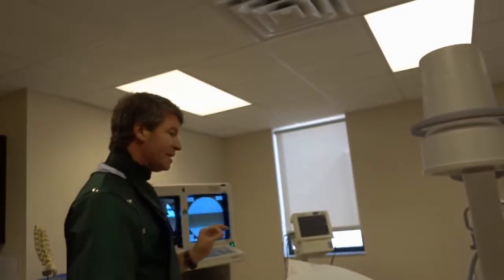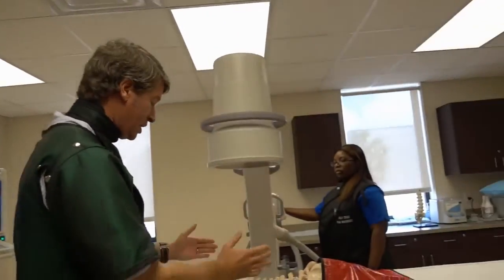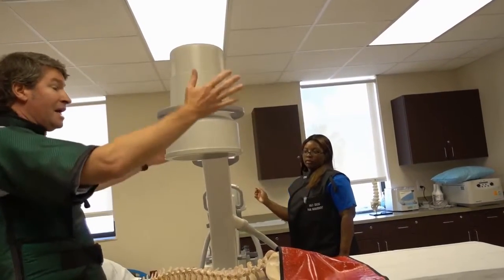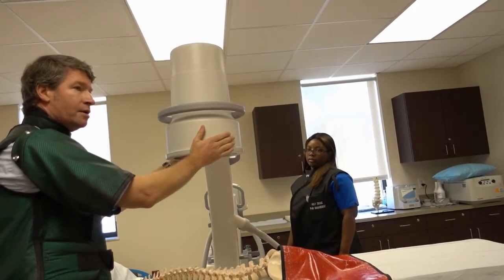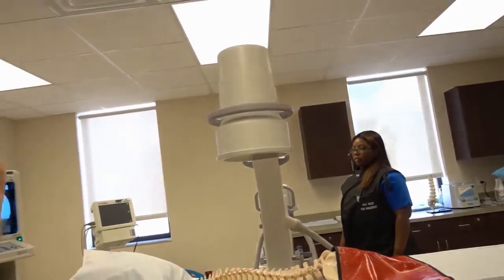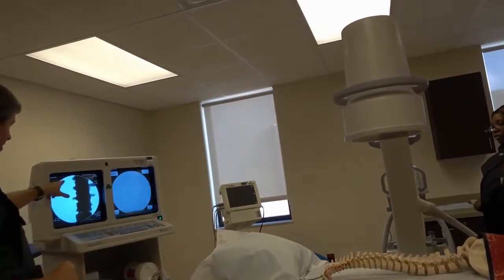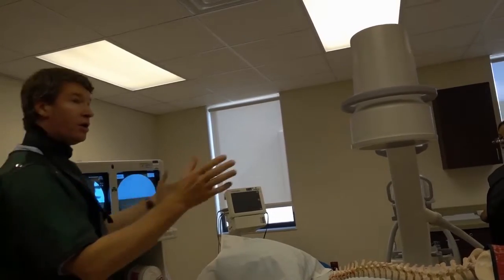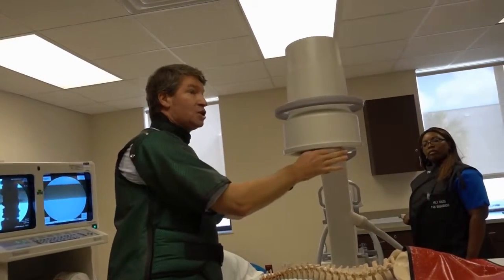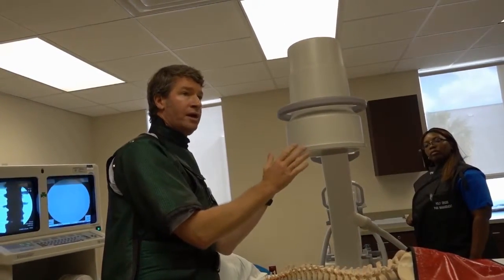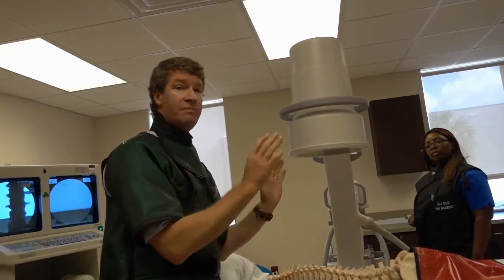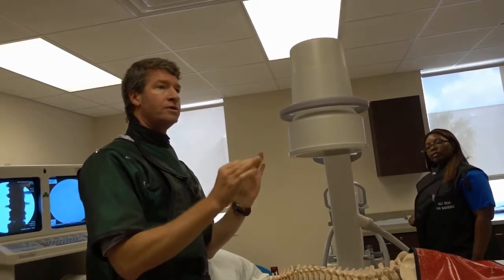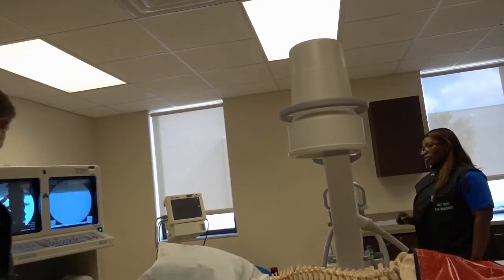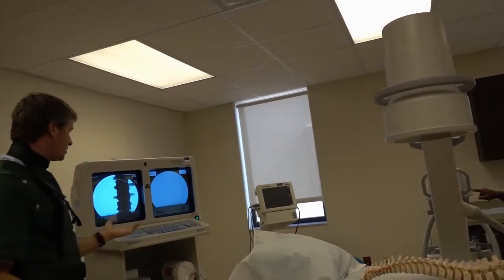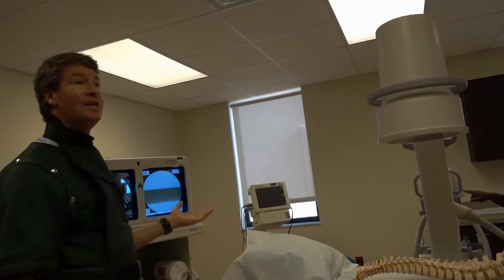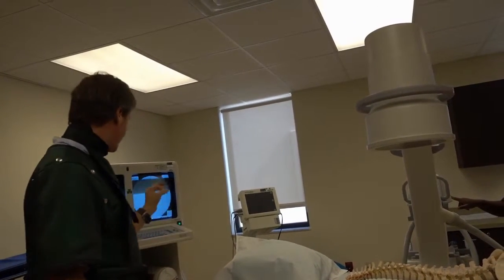Okay, so what happens is, without any collimation, the cone of light comes out here and is bigger than the image intensifier. With one button press, just collimate one click, you can see it comes down here just a little bit. All of a sudden it went from out here to this. So one click of the collimator will cut your radiation by almost 50%, which is major. So always, always, always collimate. And even more, let's say we collimate down here, you will cut the exposure down really almost 60, 70, 80%, maybe even 90% with very tight collimation.